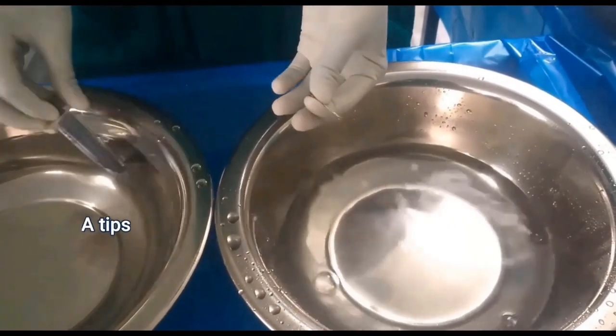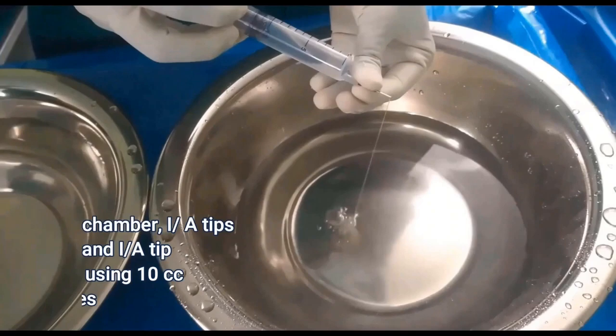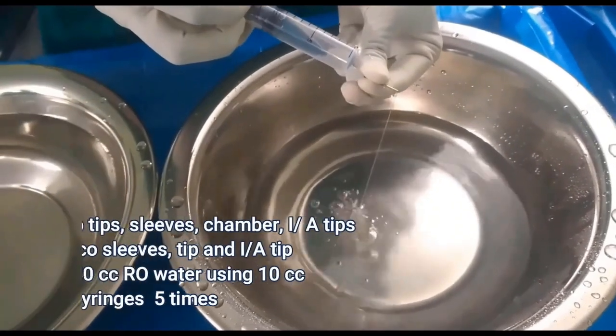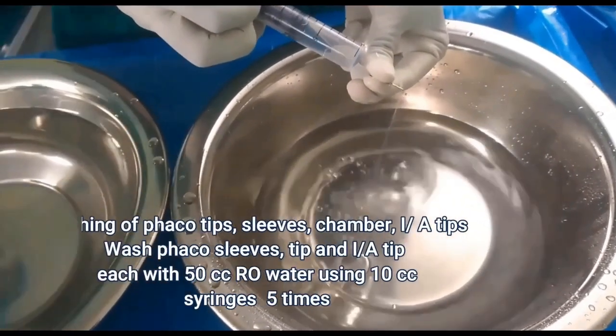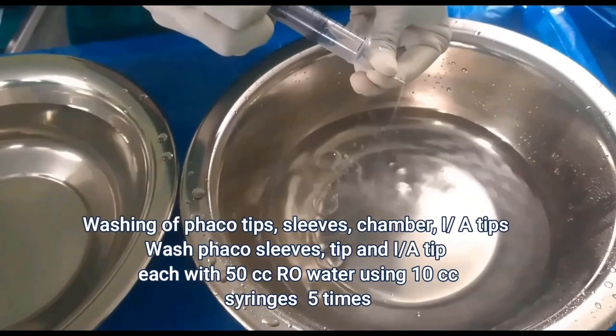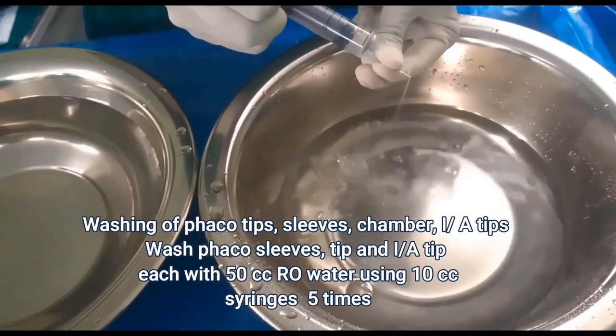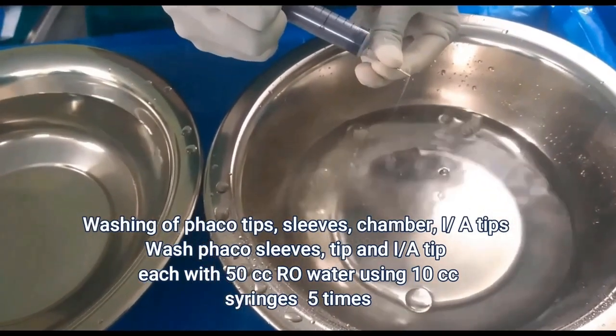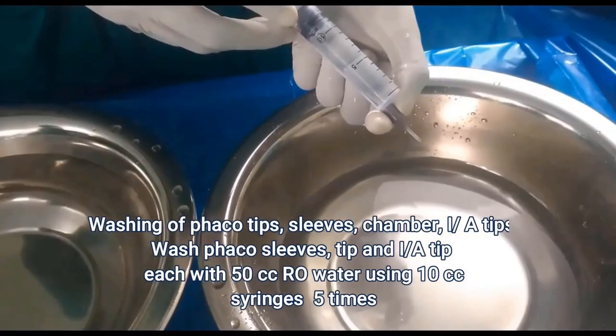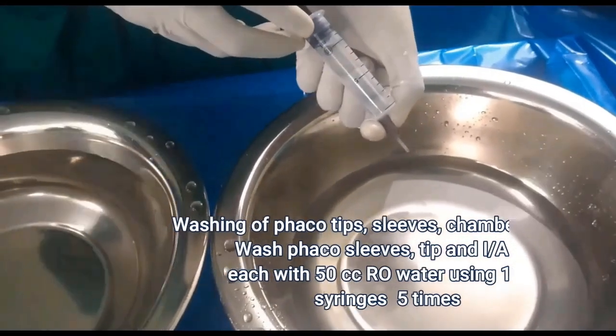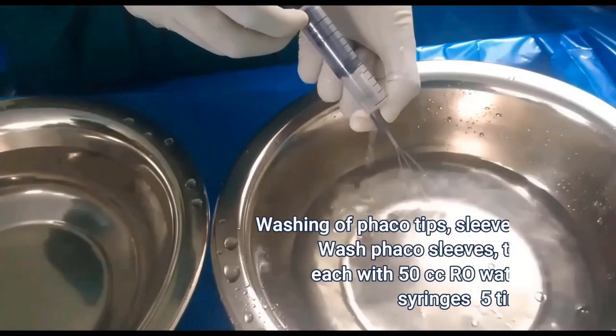Then comes washing of phaco tips, sleeves, chamber, and irrigation aspiration tips. Wash each cannulated instrument with 50 cc of RO water. That is, using a 10 ml syringe, flush 10 ml of water inside the cannulated instrument 5 times.